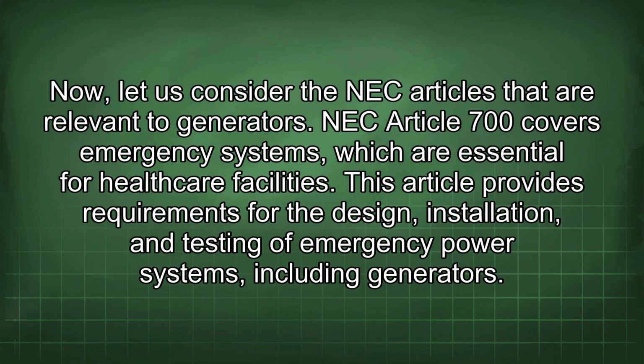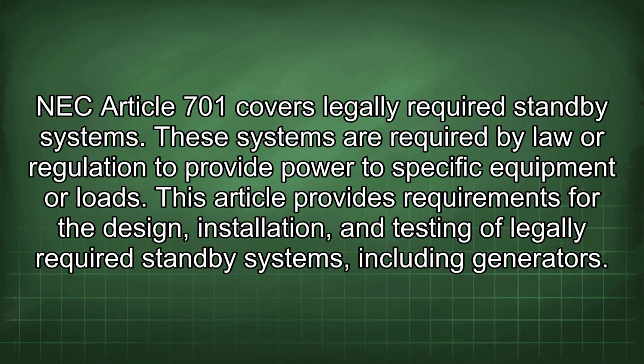Now, let us consider the NEC articles that are relevant to generators. NEC Article 700 covers emergency systems, which are essential for healthcare facilities. This article provides requirements for the design, installation, and testing of emergency power systems, including generators. NEC Article 701 covers legally required standby systems. These systems are required by law or regulation to provide power to specific equipment or loads. This article provides requirements for the design, installation, and testing of legally required standby systems, including generators.